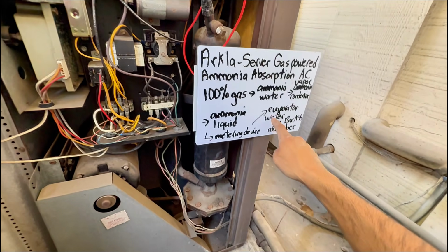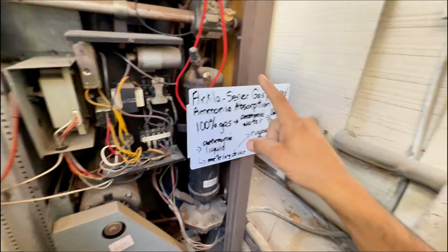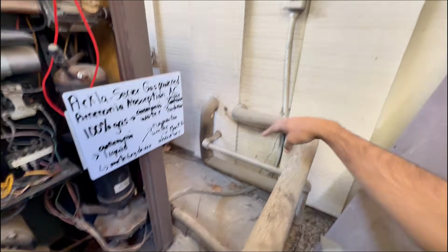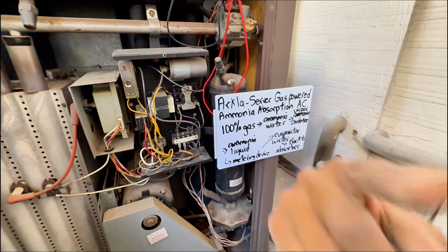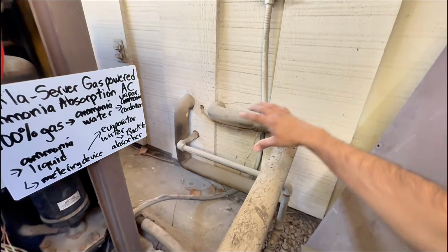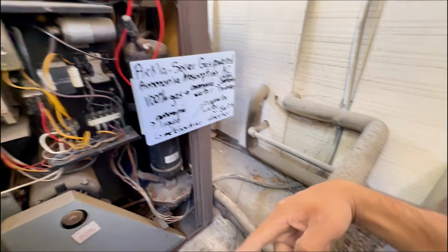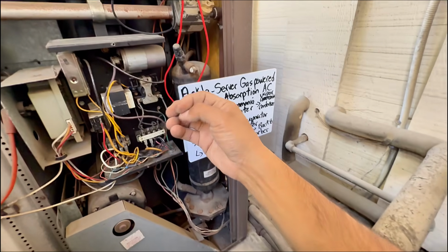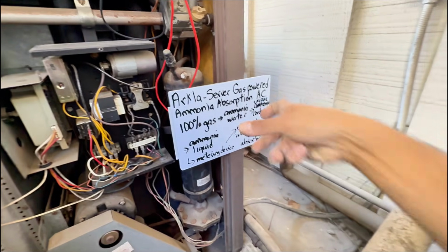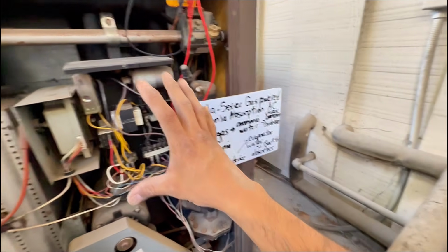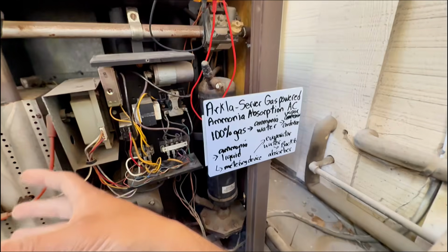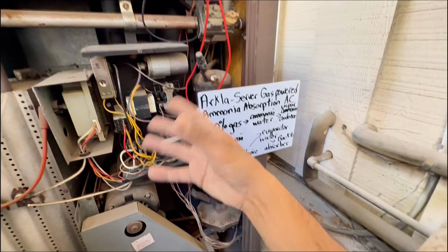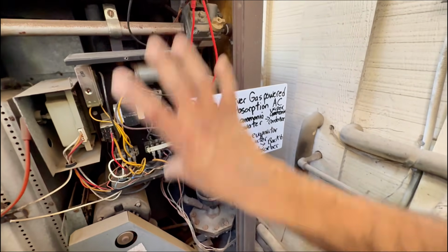So basically, that ammonia in your evaporator is low pressure, low temperature, but you don't have the refrigerant going all the way inside. What it's doing is you're using water to create a heat transfer with the evaporator. So let's say you have, just as an example, 50 degree, 60 degree water coming this way. It goes to that evaporator where it has that cold ammonia refrigerant, right, cold. And that water, with the ammonia, you're boiling off that liquid refrigerant and the water's coming back cold, right? Same thing as the air, right? Air to refrigerant. Warm air goes to the evaporator. You're boiling off all that liquid refrigerant, but then the air coming out is cold. Same thing, you got warm water, boiling off all that saturated ammonia refrigerant, so that we can have vapor coming out.